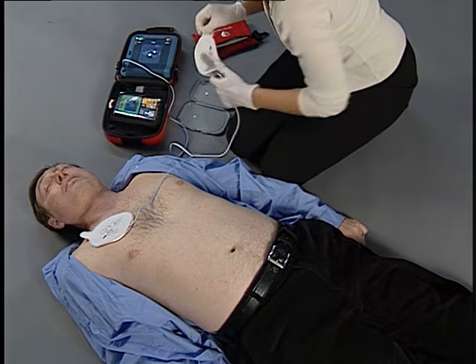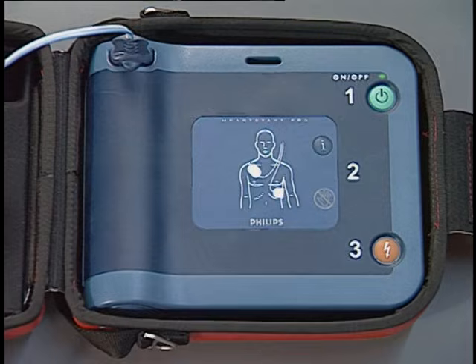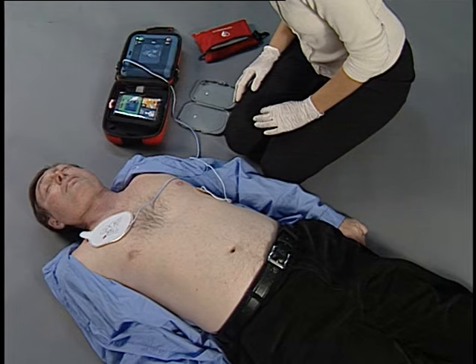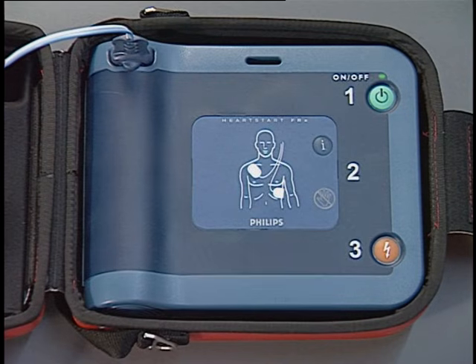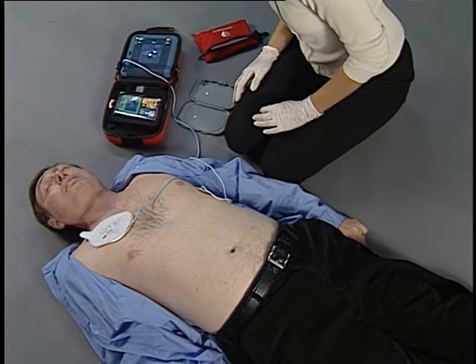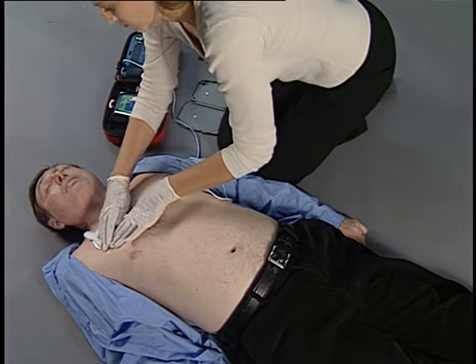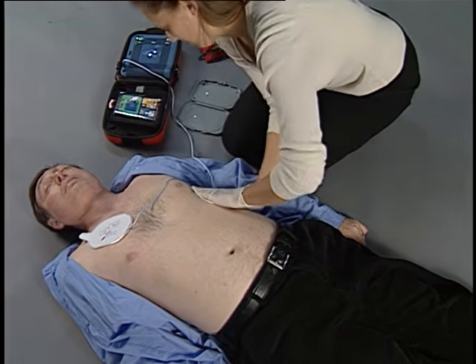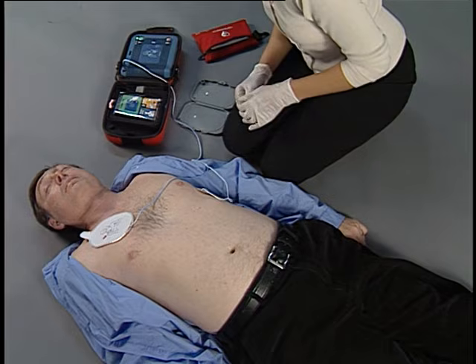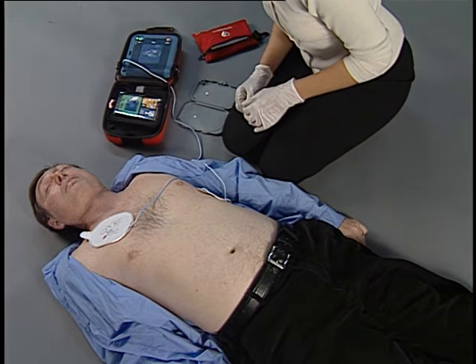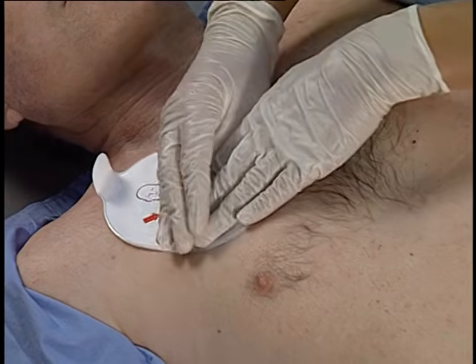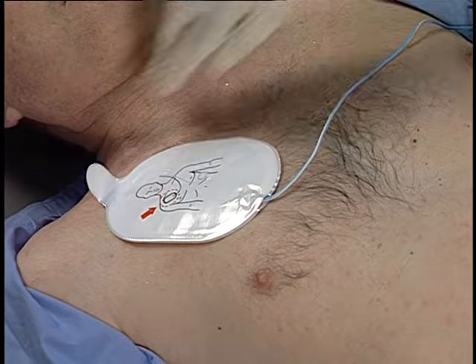If the FRx detects a problem while you are using it, it will provide a voice instruction to guide you in correcting the problem. If this happens, stay calm and follow the defibrillator's instructions. Press pads firmly to patient's bare skin. For example, good pads contact is key. The FRx tells you if the pads are not making good contact and directs you to press the adhesive pads firmly onto the patient's bare skin.